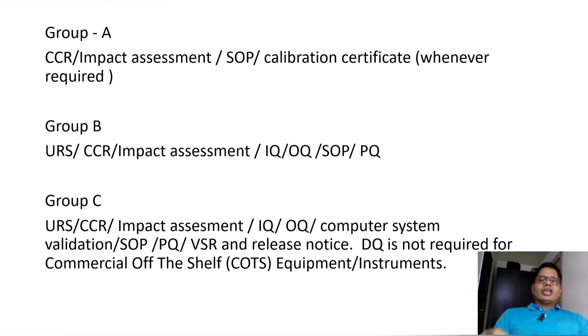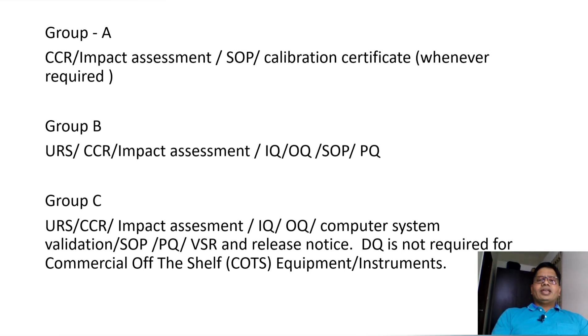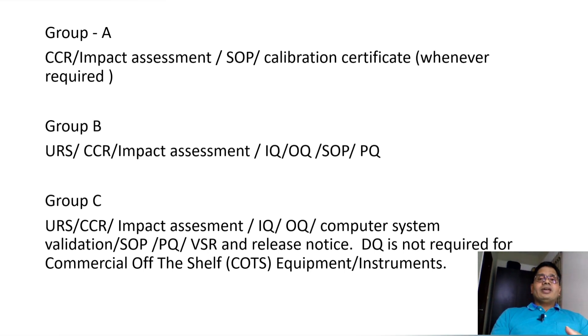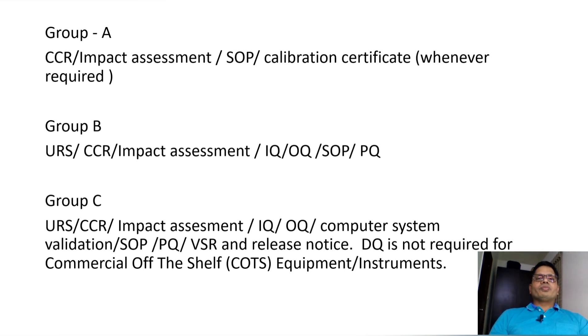Design qualification is not required for commercially available equipment. For Group C instruments, design qualification may apply in some cases, but for instruments readily available in the market — such as HPLC, GC, FTIR, or UV — design qualification is not required. However, if you are procuring a custom stability chamber, then yes, design qualification should be performed. Based on the system boundary and your organization's master validation plan, you determine the qualification requirements for Group A, Group B, and Group C instruments.